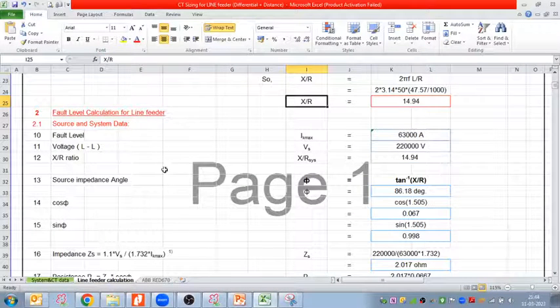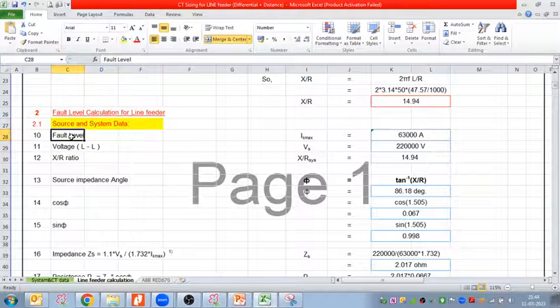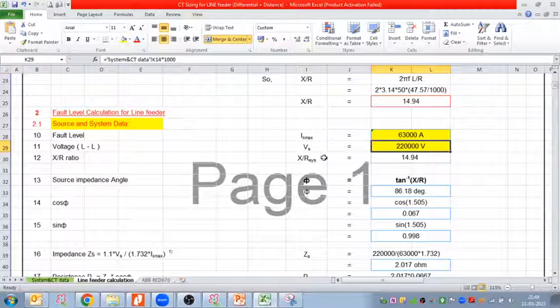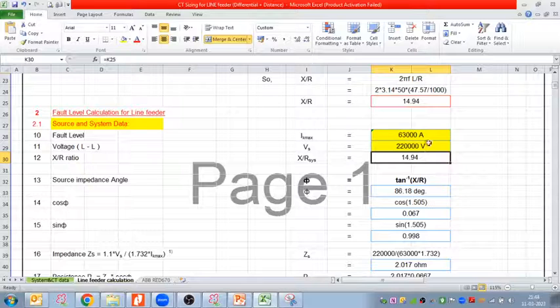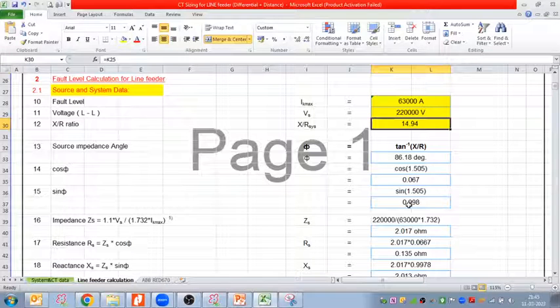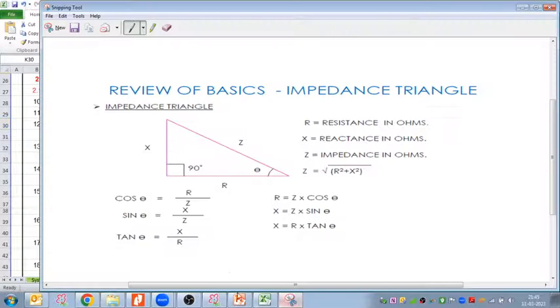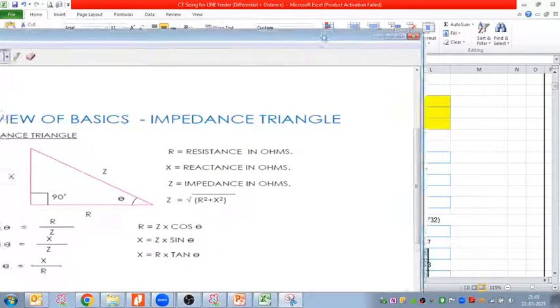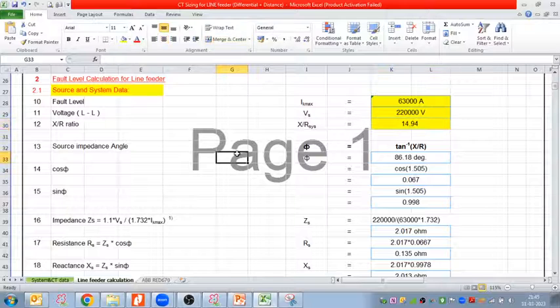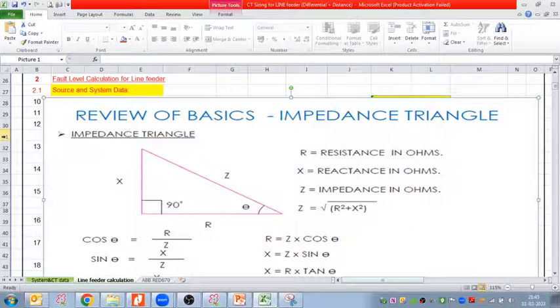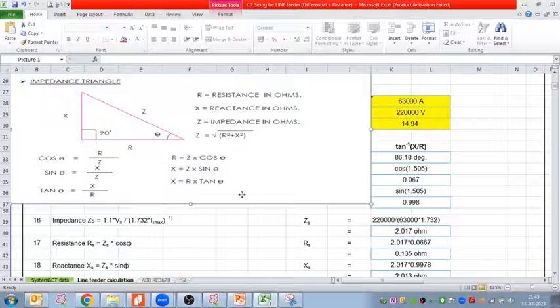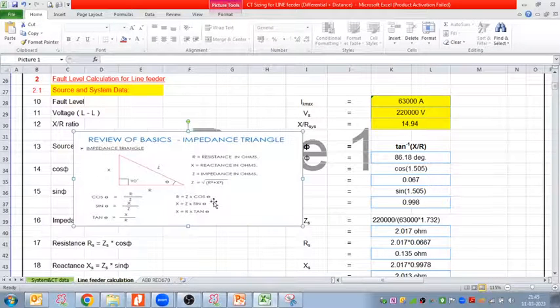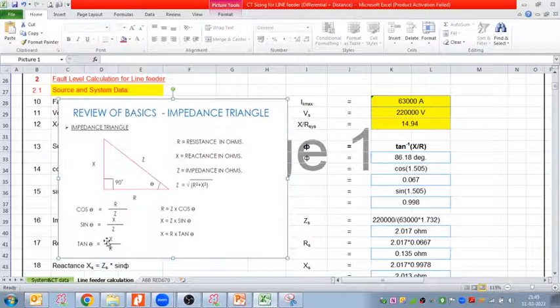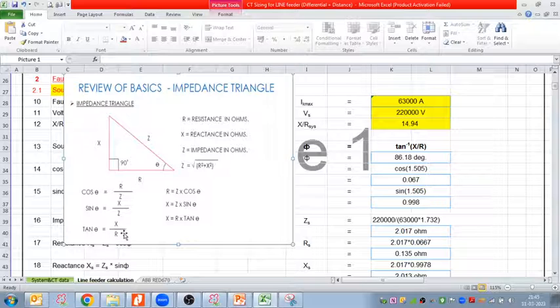Fault level calculations for line feeder. So source and system data we are now calculating. Fault level of the source 63 kiloampere, 220 kilovolt, so convert into the same unit, ampere and voltage, and source X by R is 14. Now this is all your impedance triangle formula. So as per this impedance triangle formula, let me just take this snapshot and paste here. Yeah. So theta, how much? We know the X by R, so we can find out the theta.